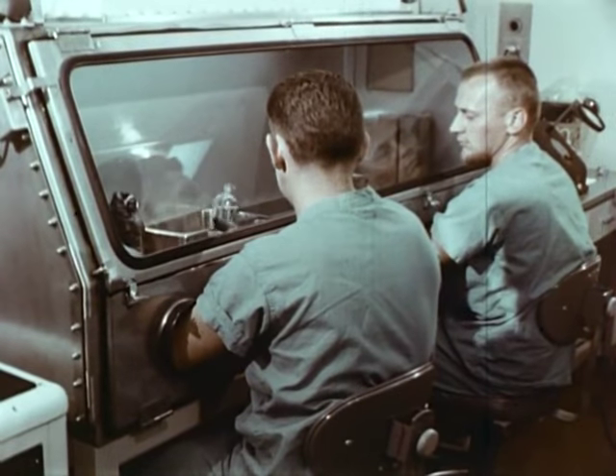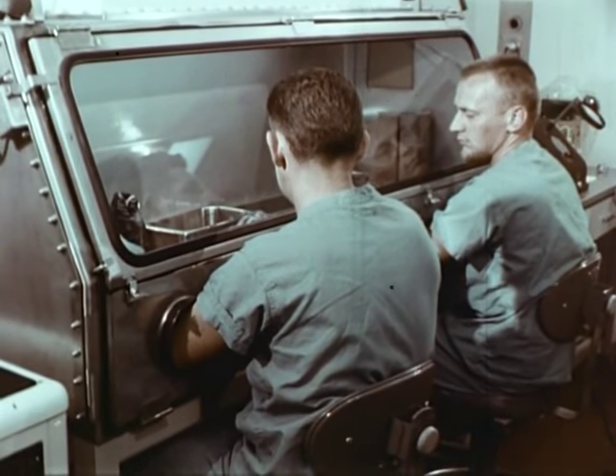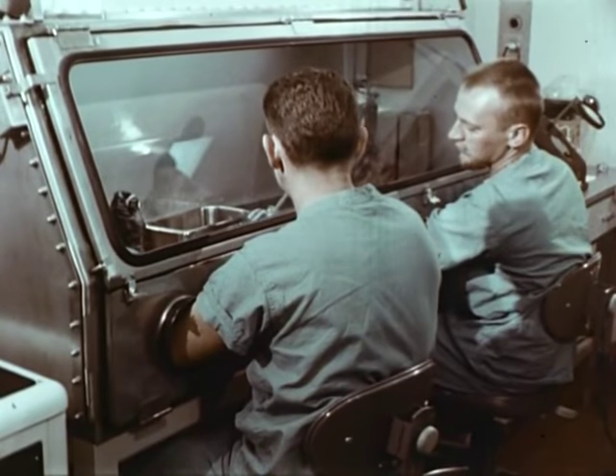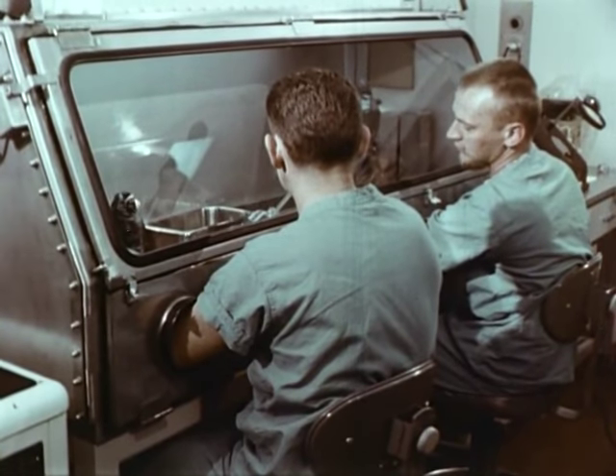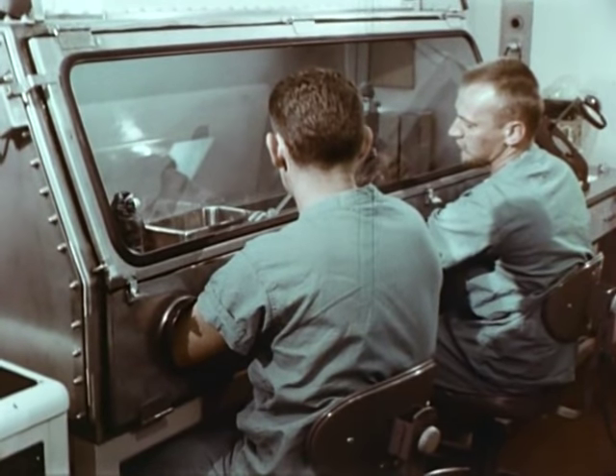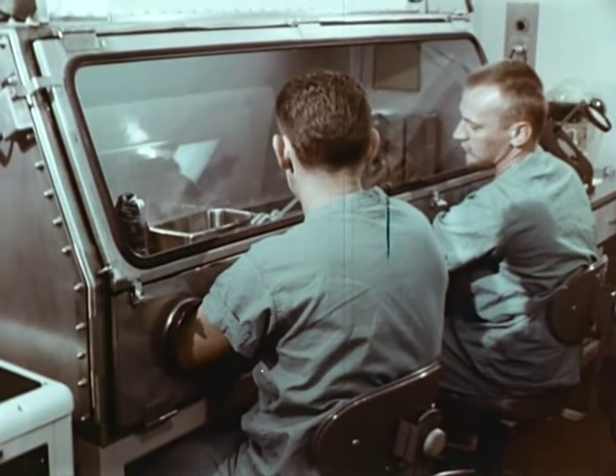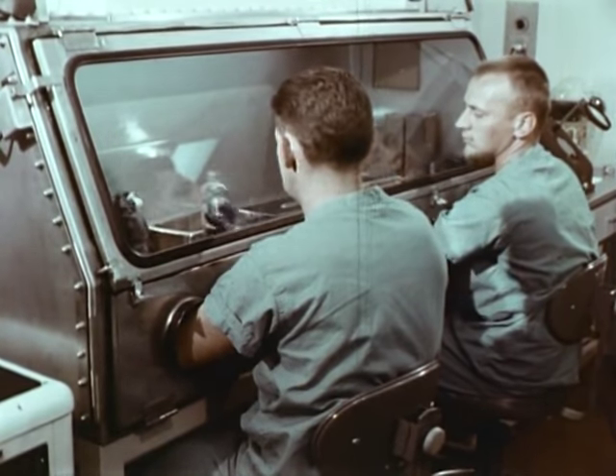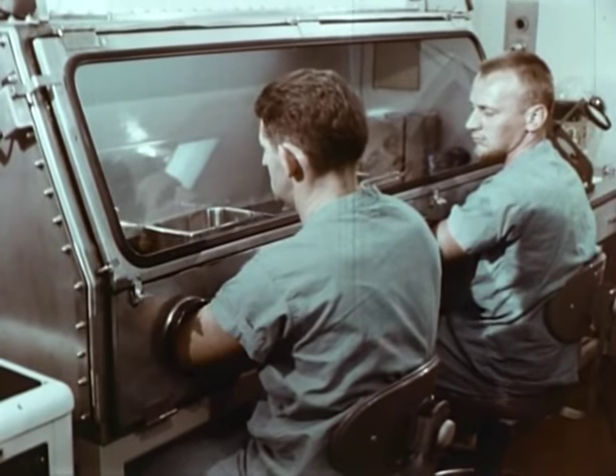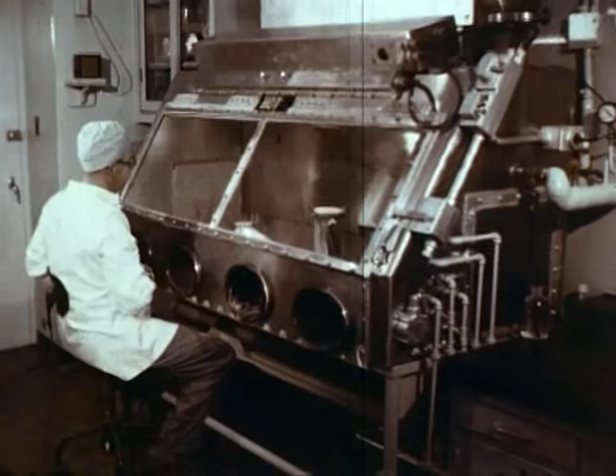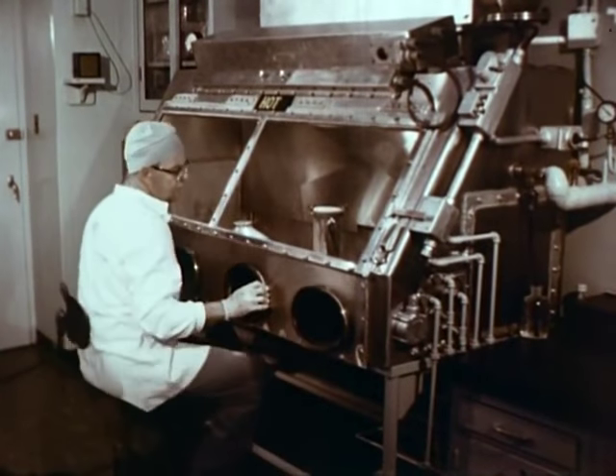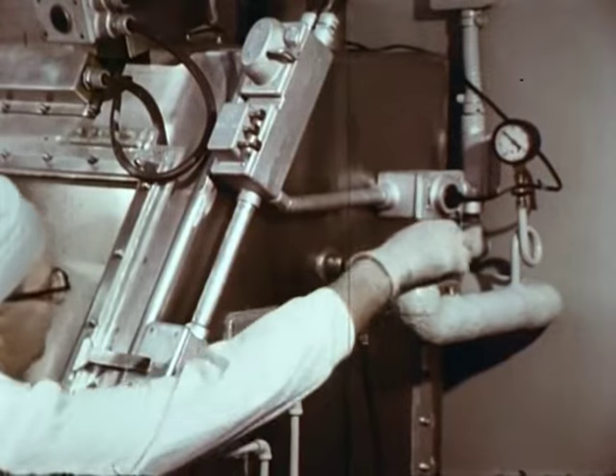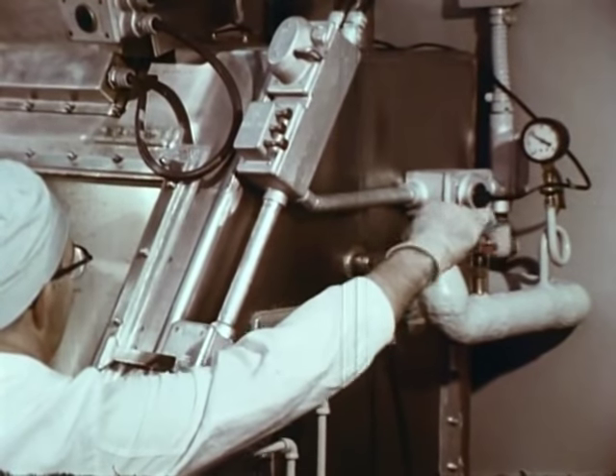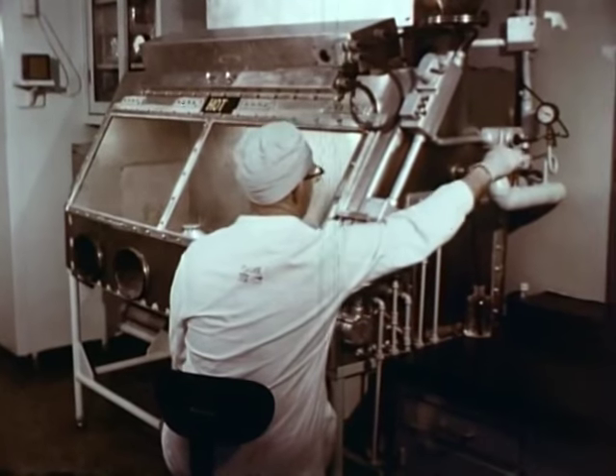Some partial barrier cabinets are equipped with front panels with attached arm-length rubber gloves to provide a greater degree of microbial control. With this cabinet, there is a saving in operating cost, since it requires very little conditioned air as compared to that needed for the open face type. Steam is one of the desired services and is used with formaldehyde to decontaminate both the inside of the cabinet and its exhaust air filter.